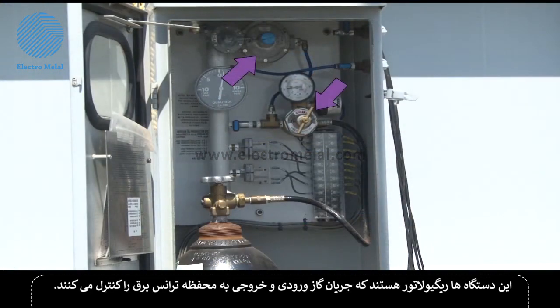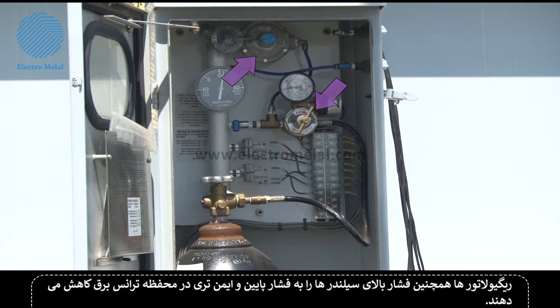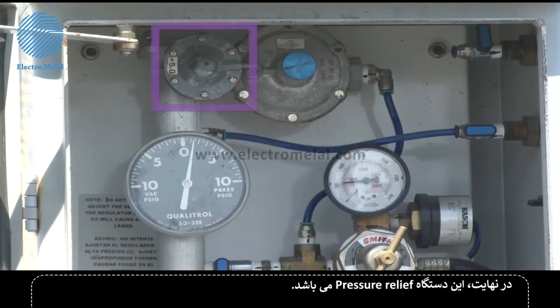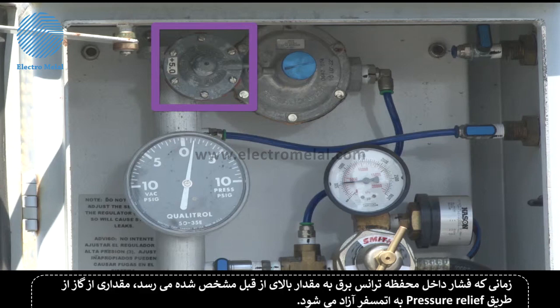These devices are the regulators. The regulators control the flow of gas to and from the transformer enclosure. The regulators also reduce the high pressure from the cylinder to a safer, lower pressure in the transformer enclosure. Finally, this device is a pressure relief device. When the pressure inside the transformer enclosure exceeds a predetermined high value, some of the gas in the enclosure is released through the pressure relief device to atmosphere.